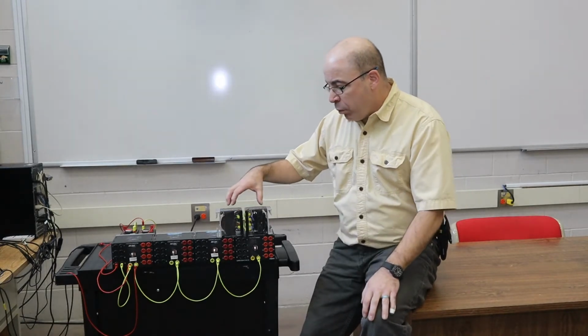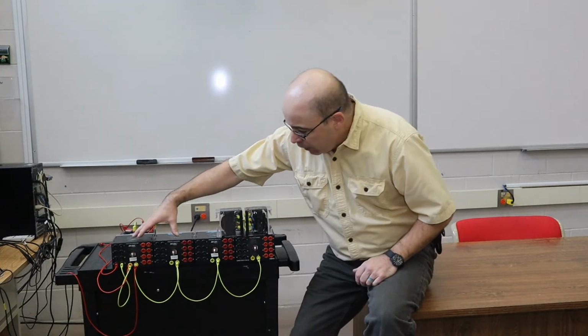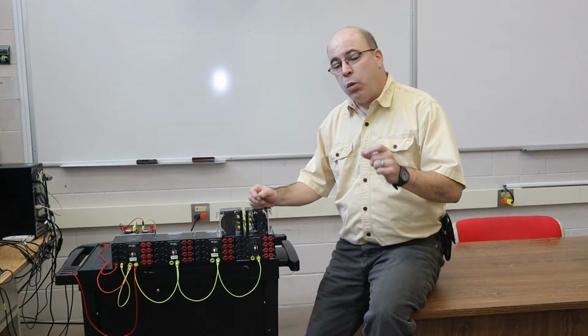Now, what are some of the problems associated with undersizing a control transformer? When we look at the various relays, and here I've got contactors from the lab volt workstations, to try and demonstrate that when we don't size our control transformers accurately, we're going to have problems with our control circuits. Namely, that my relays are not going to energize and pull in because the relays are basically air core inductors at the point in time when we activate or energize our control circuit. And due to that fact, they require an awful lot of apparent power on startup.